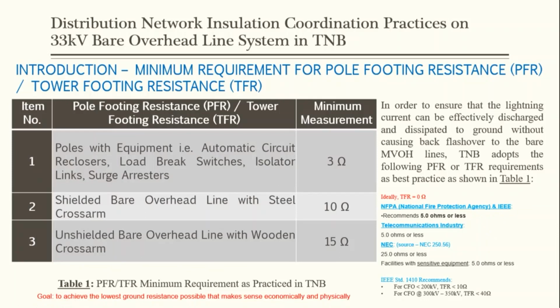NEC 250.56, 25 ohms or less, but facilities with sensitive equipment should be 5 ohms or less. And IEEE standard 1410 recommends that for any CFO less than 200 kV, the TFR or PFR should be 10 ohms, and for CFO at 300 kV to 350 kV, the TFR should be less than 40 ohms.